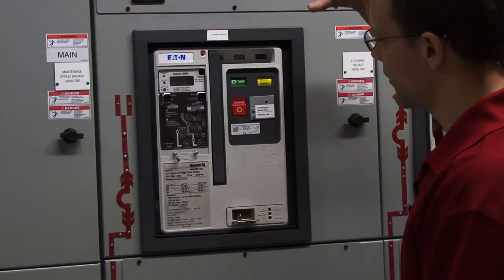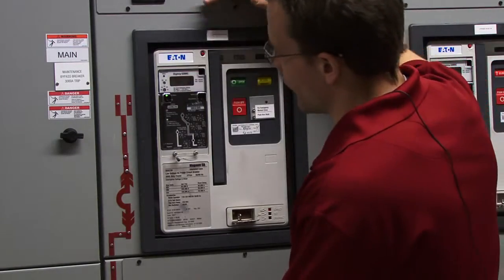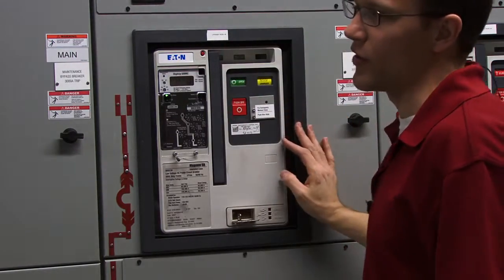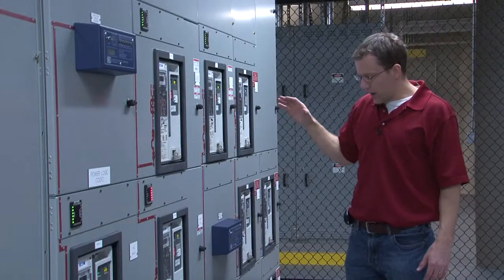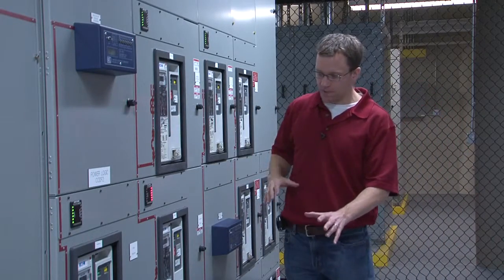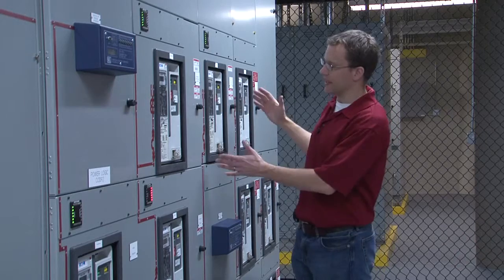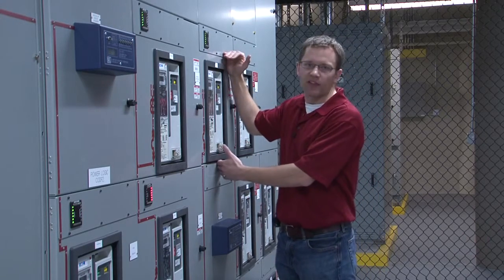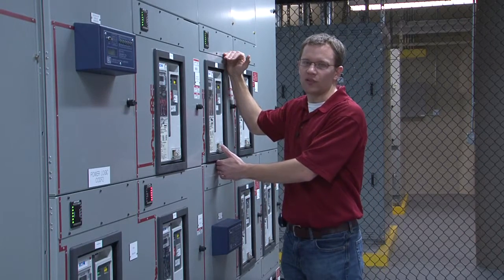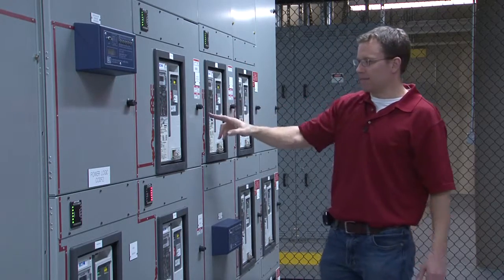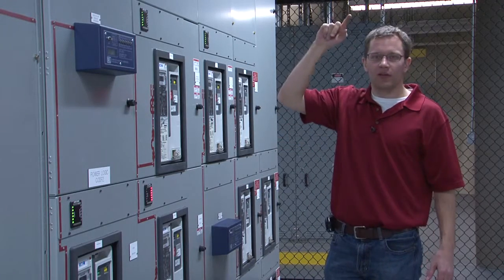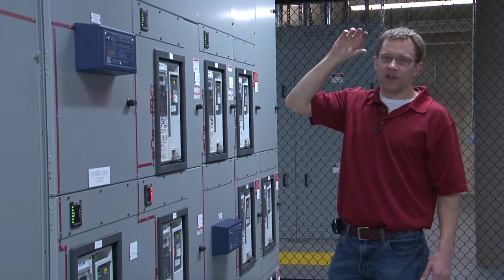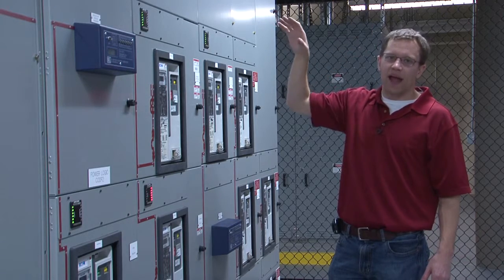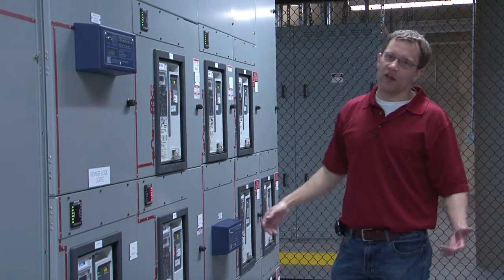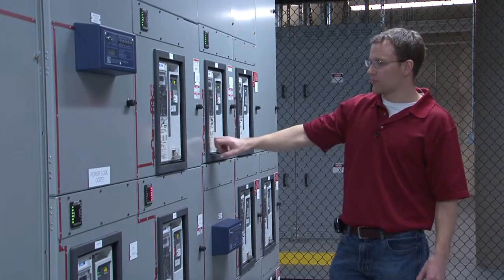There's a sync check that checks voltage synchronization across here, and if you use the button to close the breaker, you defeat the sync check relay. So when you're in maintenance bypass, that's the only time that it's possible to operate this breaker using the Square D system. But it feeds out to MS3, which then feeds the load bank, and you would apply load to an offline UPS system through this breaker.